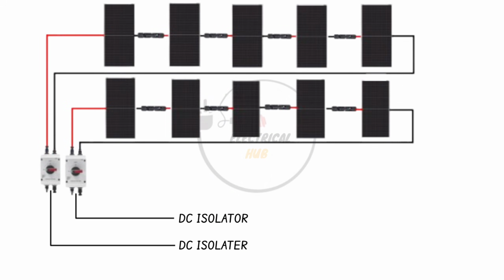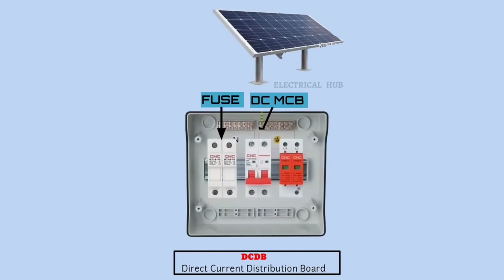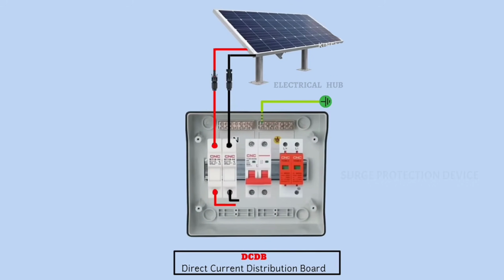DC isolator. A DC isolator is a disconnect switch for a solar string. It is a safety device that allows you to manually disconnect the solar panel from the rest of the system. This is important for maintenance, repairs, or in case of emergency. DC distribution board (DCDB). A DC distribution board is a panel that houses DC circuit breakers (MCBs), surge protection devices (SPDs), and other components to distribute DC power safely and efficiently.